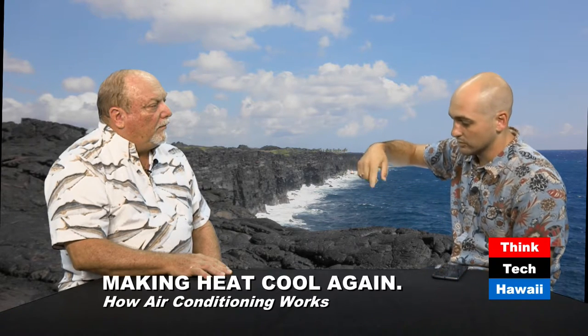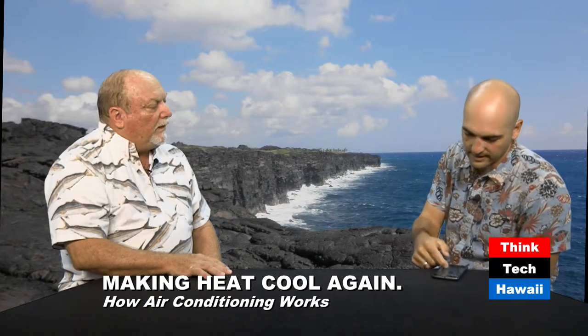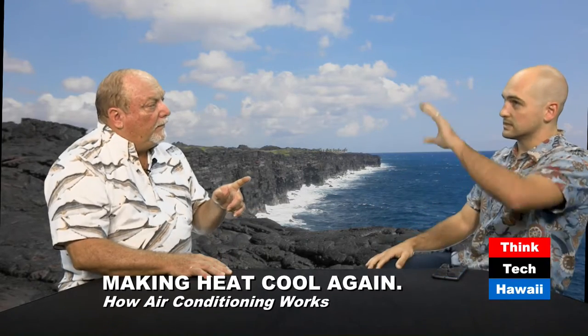On the other side of the tank, we're doing the same thing, pushing water back down over what will then be our cool side, and having that expand. Is this a separate loop? It's a separate loop, yep. So this water side, which was the condensing and evaporative side, is very similar to what we showed before. That's where you expand, and instead of blowing air across it, these are typically coils that you're spraying water on—showering water, like a chiller unit.